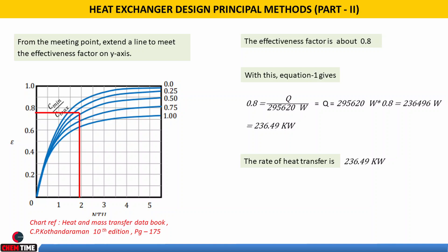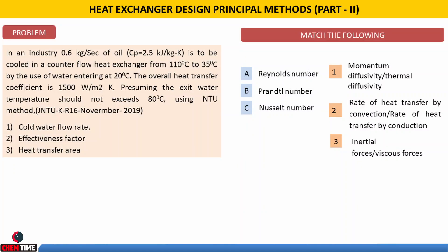These graphs are available for both parallel flow and counter flow configurations. For counter flow, refer to 'Heat and Mass Transfer Data Book' by C.P. Kothandaraman, 10th edition, page 175. Locate NTU = 1.95, draw a vertical line to meet the C_min/C_max = 0.4 curve, then draw a horizontal line to read the effectiveness ε = 0.8. Since ε = Q / Q_max and Q_max = C_min × (T_H,in − T_C,in) = 295,620 W, Q = 0.8 × 295,620 ≈ 236.49 kW.